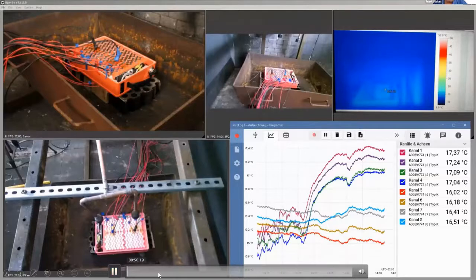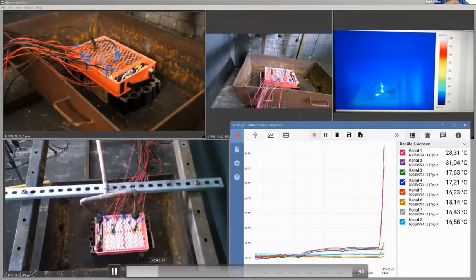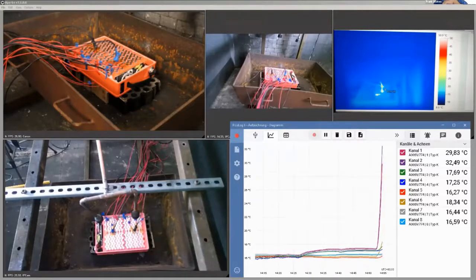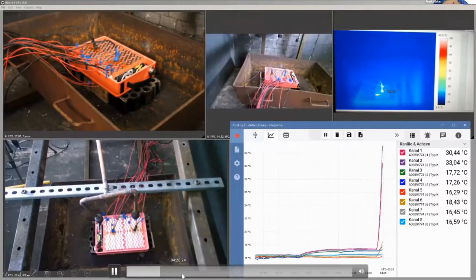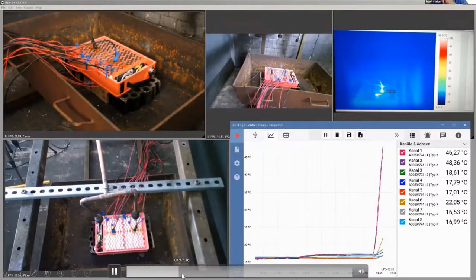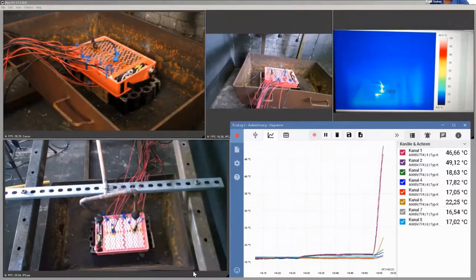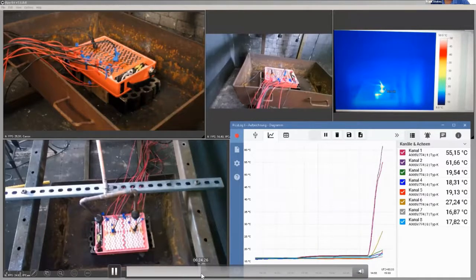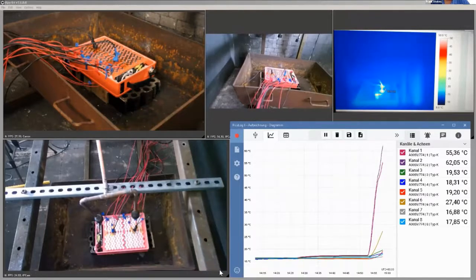I'm going to speed through this. As you can see top left, a little wisp of smoke coming out. Pay attention to the graph on the right - you start seeing changes in temperature. Top right, on the thermal imager, the heat starts building up, and you see on the graph just below, the rising temperature. Still nothing really visible from the outside.